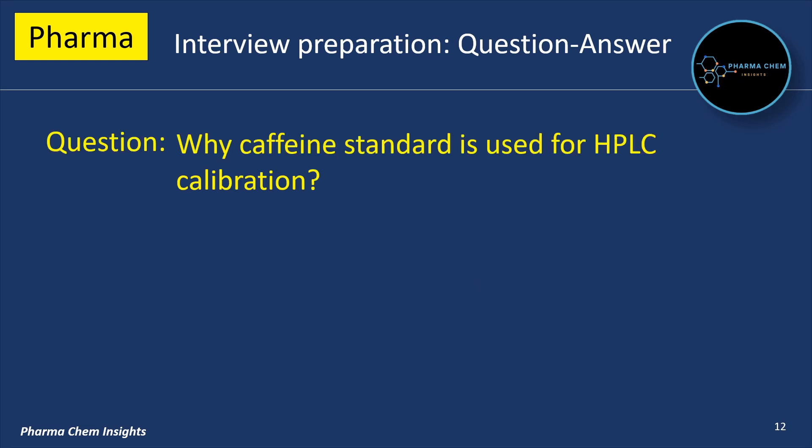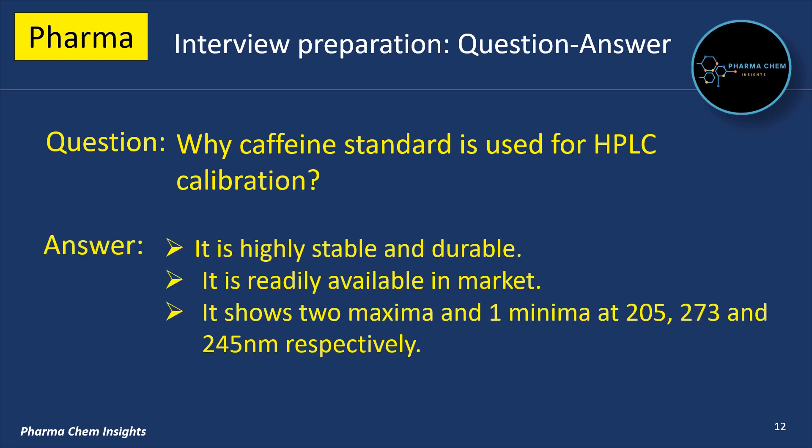Next Question: Why is caffeine standard used for HPLC calibration? Caffeine standard is used because it is highly stable and durable, it is readily available in the market, and it shows 2 maxima and 1 minima at 205, 273 and 245 nanometers respectively.